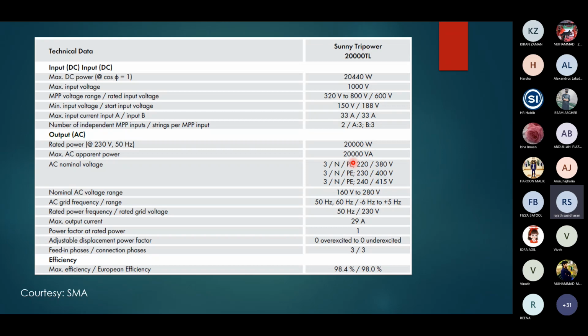Then it just gives you more AC insights, like how much power it can produce in volt amperes. The inverters can give you a certain amount of reactive power also, along with the active power, just to improve the quality of power to pump into larger distances. And according to the grid demand, the larger scale photovoltaic plants can give like 300 megawatt or 400 megawatt reactive also, according to the grid needs. And it gives you the nominal voltage ratios under which it can perform well. And you can simply go through this.